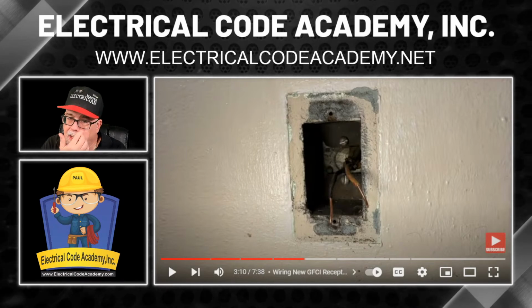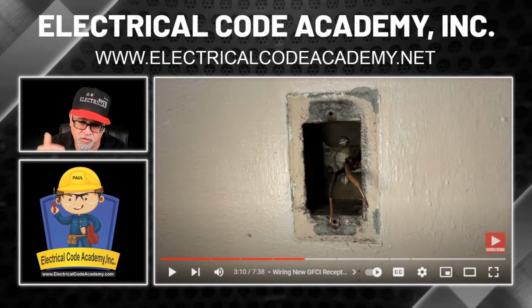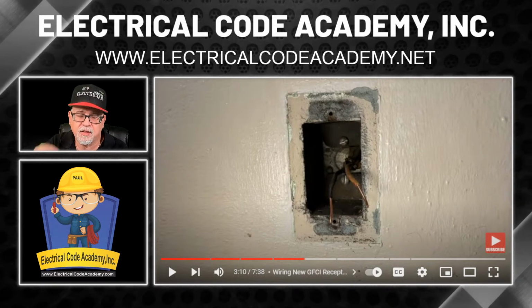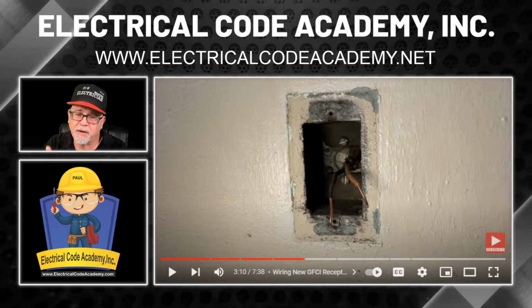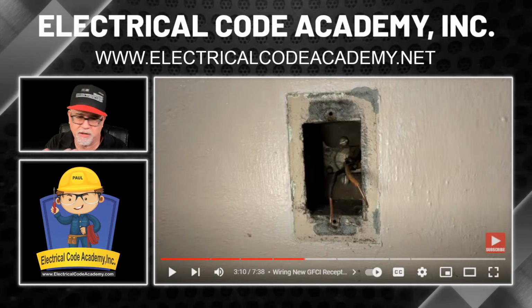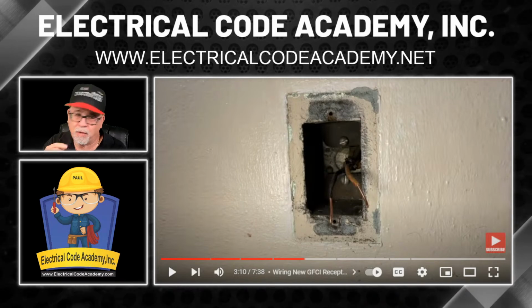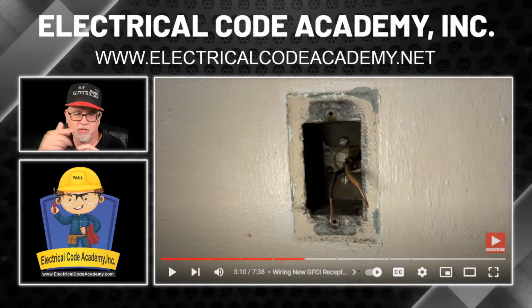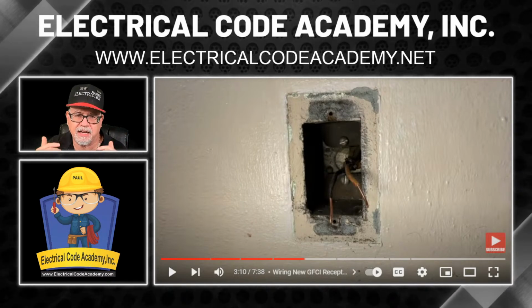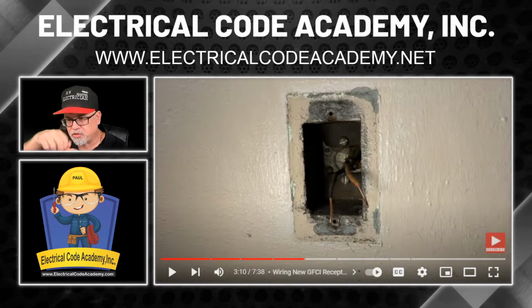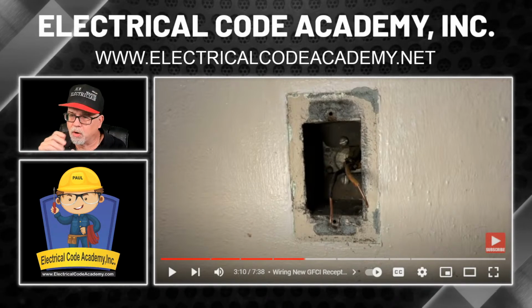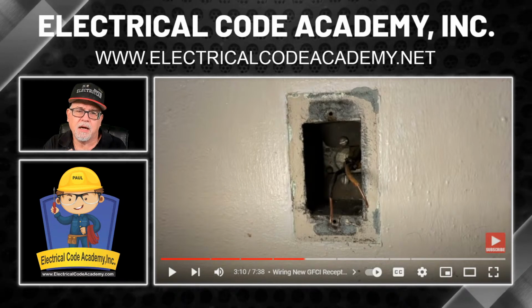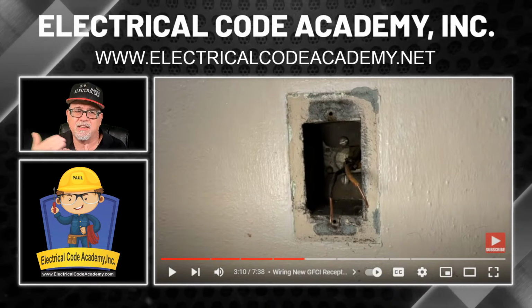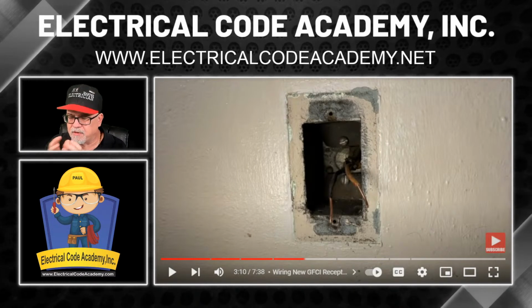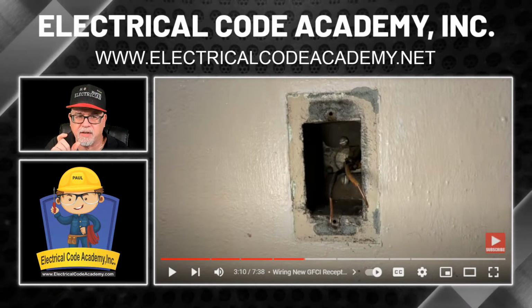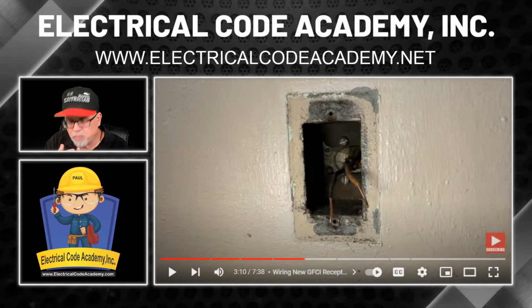Secondly, cutting those shepherd hooks off the end of the wires, when they could have probably been reused. The chances are they weren't damaged. I would have taken the screws all the way out, just worked them all the way out so they fall out of the device, and then looked at it and either straightened it out, or you could have cut it off. But again, you want to preserve the length that you have because you need it. This device is rather deep, right? The GFCI, and I have to have enough room to work with it.